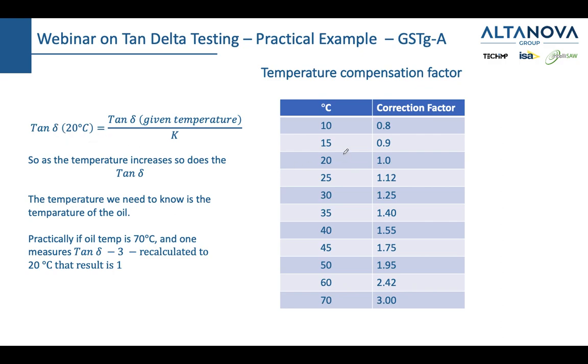You see, if tan delta at 20 degrees Celsius is 1, it is the same as having tan delta of 3 at 70 degrees Celsius. So what you need to find out is the temperature of the oil on your transformer. You simply read it from the gauge which is installed on the transformer and you factor that in after you measure the tan delta. Because if it's 50 degrees outside and you got, let's say, 1.8, it doesn't mean that your high voltage transformer has a problem. It simply means that you need to compensate for that temperature using this formula here. So I hope that is clear.